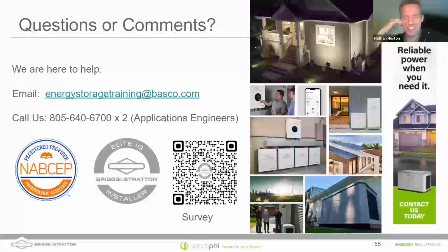Yes and no. If we AC couple through the loads port and have a generator connected, we would have to have a lockout module that locks the AC coupled solar out when the generator's running. Otherwise, the AC coupled solar, basically the gen port is connected to the load port when that generator is running, right? So you can do it, but you need a lockout module to prevent the AC coupled solar from coming in. So that's a great question.